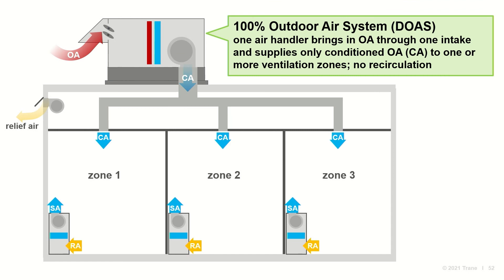In a 100% or dedicated outdoor air system, one air handler serves the ventilation needs of more than one zone. Outdoor air enters through the intake and is delivered to the zones without mixing with any recirculated air — the dedicated outdoor air unit delivers only outdoor air, not a mixture of outdoor and recirculated air.